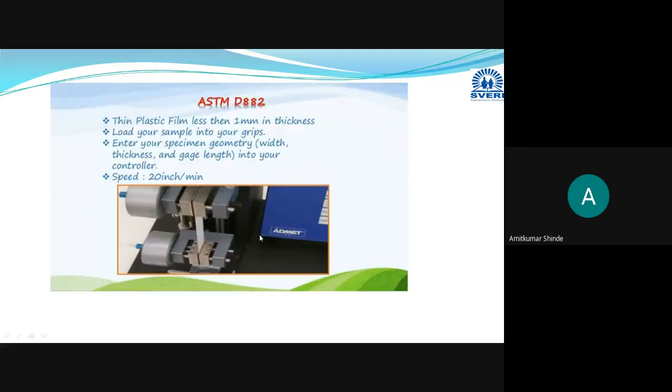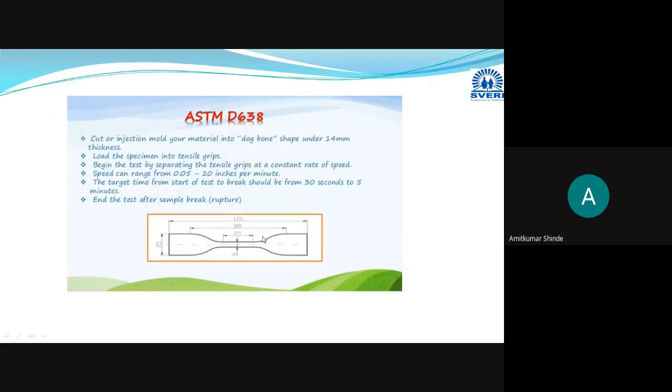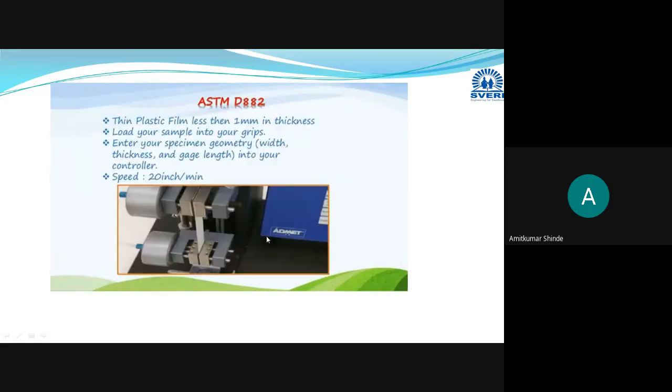Now here, one more tensile testing I have collected for very thin plastics, having thickness less than 1 millimeter. For them, this automated tensile machine is there.